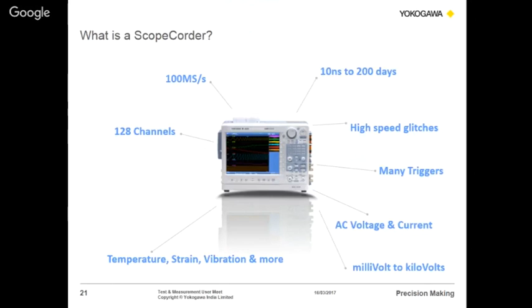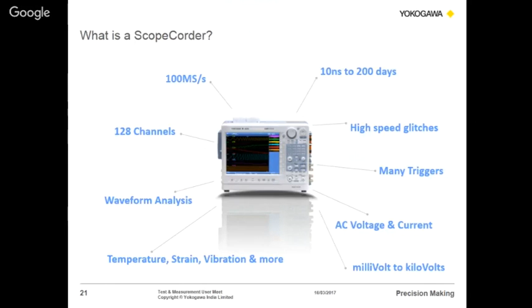So it can not only measure voltage and current, it can also measure temperature, strain, vibration, acceleration, and frequency - many more parameters. Moreover, it can do waveform analysis. Normally, recorders will have a sampling rate of about 1 second, or the best recorder available is 500 milliseconds, but here we can have 100 mega samples per second.